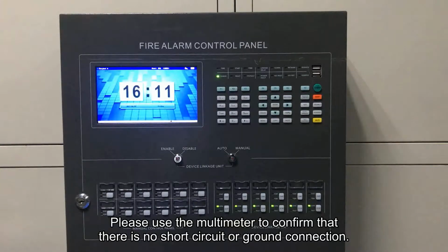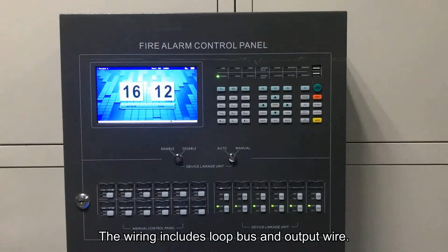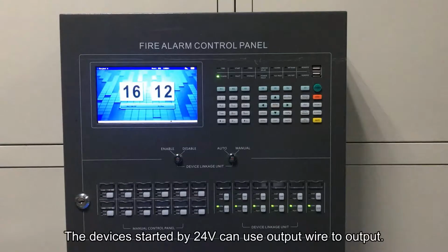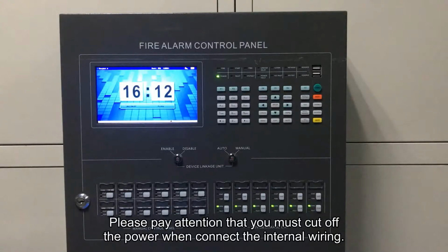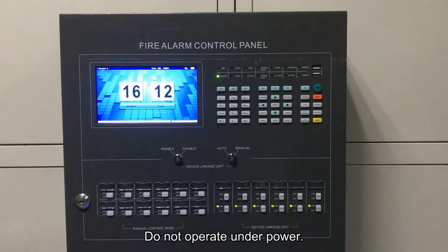Please use the multimeter to confirm that there is no short circuit or ground connection. The wiring includes loop bus and output wire. The devices started by 24 volt can use output wire to output. Please pay attention that you must cut off the power when connecting the internal wiring. Do not operate under power.